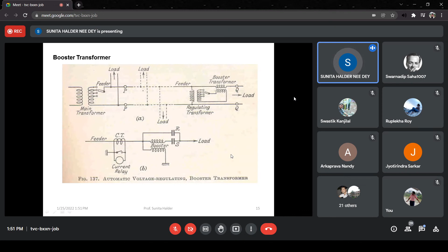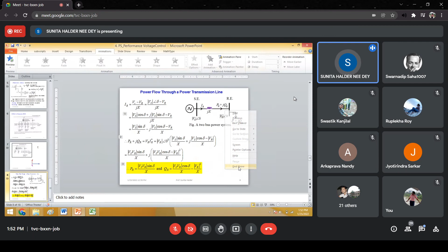So in that case, we may take the help of a booster transformer. What does a booster transformer do? A booster transformer actually inserts some series voltage in the line. Say this was a line. There was a voltage drop of 10 volt. Now due to huge current, the voltage drop has increased to 50 volt. Now if you add a voltage in reverse polarity of 40 volt, then you can maintain the same voltage. This can be done using a booster transformer. Now the voltage with negative polarity can only be added using a transformer. If the transformer secondary is there with proper polarity and the primary you energize, then only it is possible, otherwise not. So this thing is actually done using this booster transformer.